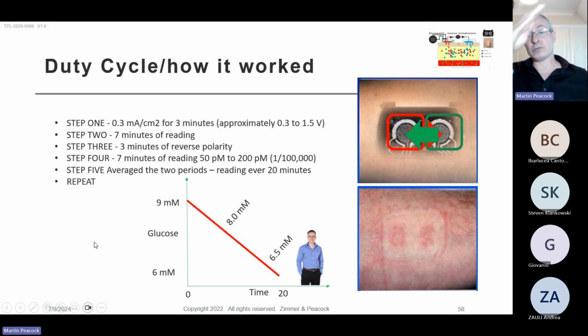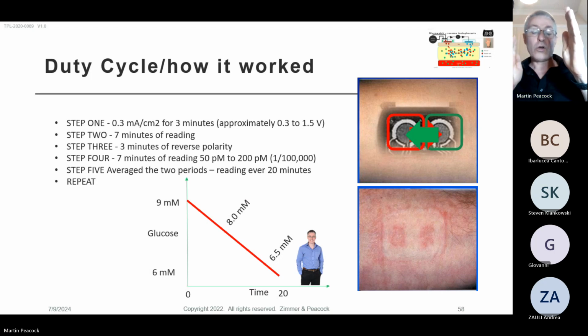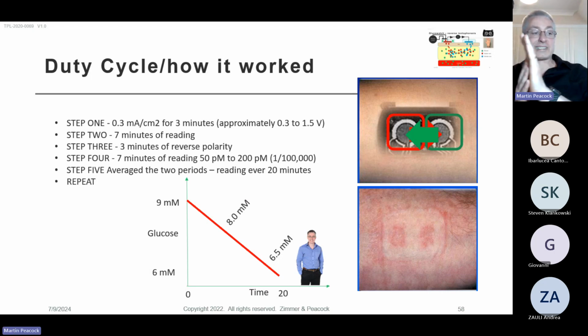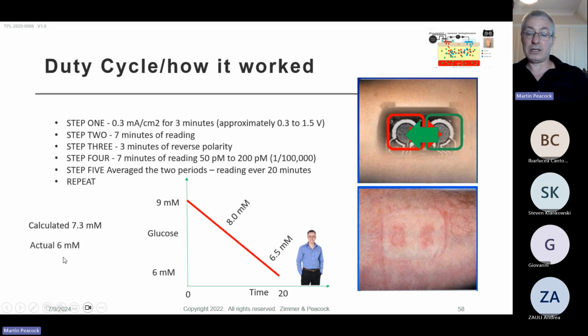But understand that if somebody was falling in their glucose level and you made a reading and then a second reading and then averaged those two readings, you're slightly misreporting what their glucose is at that moment, because you've got a history effect from the previous recording. If I measure somebody over 20 minutes and they're falling from 9 millimolar to 6 millimolar, you may end up with a calculated glucose concentration of 7.3 millimolar, when at the time they get the result, they're actually at 6 millimolar, and that would give you an 18% error. And people did report that there was an accuracy issue.